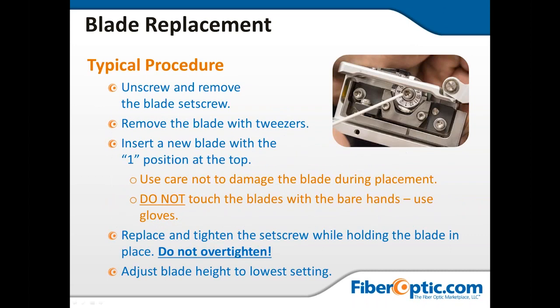Typical procedure. Unscrew and remove the blade set screw. Remove the blade with tweezers. Insert a new blade with the one position at the top. Use care. Do not damage the blade during replacement. Do not touch the blade with bare hands. Use gloves. Replace and tighten the set screw while holding the blade in place. Do not over tighten. Adjust blade height to the lowest setting.